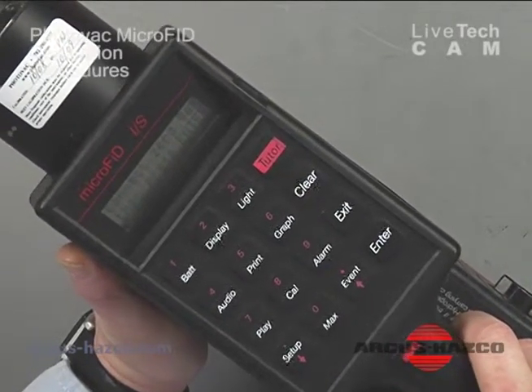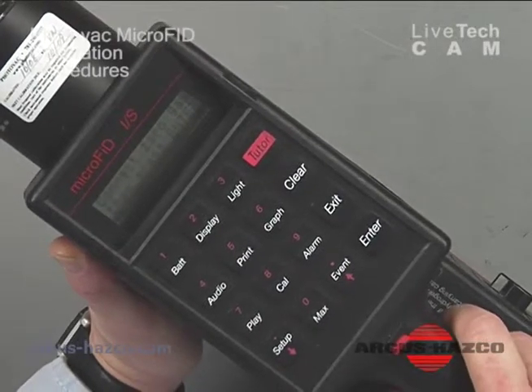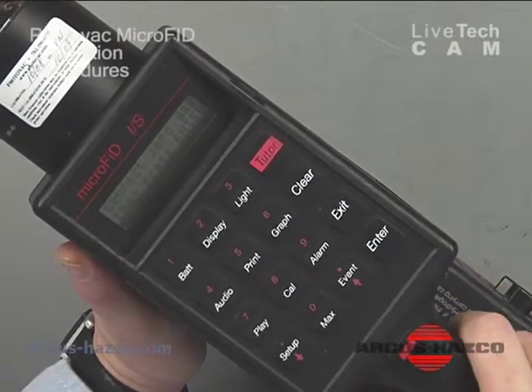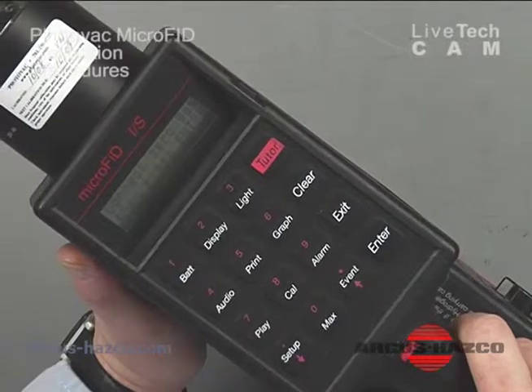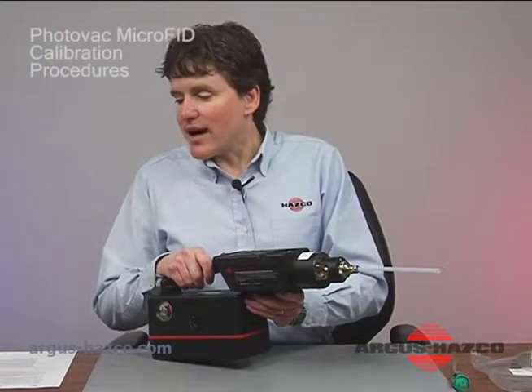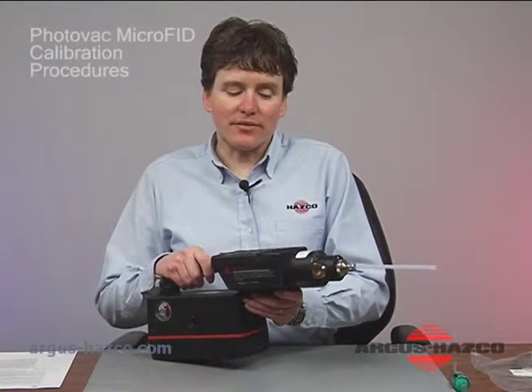But the range, you have low range and high range. And to change that range, you just use your arrow buttons. We go ahead and select low range because that's between 0 to 2,000 ppm. Then our high range will have the unit go all the way up to 50,000 ppm. But for our general purposes here, we select low range.